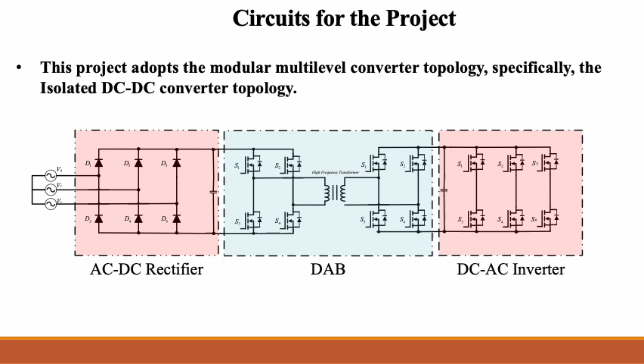A single dual active bridge circuit was first modeled in Simulink to take an input of 1,100 volts DC and produce an output of 400 volts DC. 10 of these were later connected together, and the resulting circuit handles 11,000 volts.